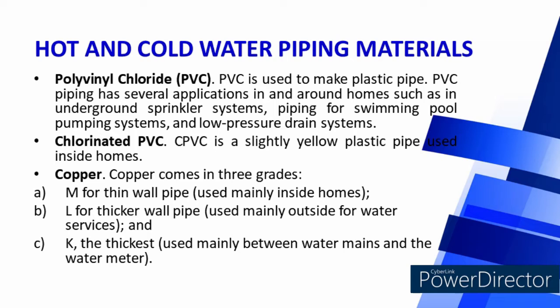Hot and Cold Water Piping Materials: Polyvinyl Chloride (PVC) is used to make plastic pipe with applications such as underground sprinkler systems, swimming pool pumping systems, and low-pressure drain systems. Chlorinated PVC (CPVC) is a slightly yellow plastic pipe used inside homes. Copper comes in three grades: Type M for thin wall pipe used mainly inside homes; Type L for thicker wall pipes used mainly outside for water services; and Type K, the thickest, used mainly between water mains and the water meter.